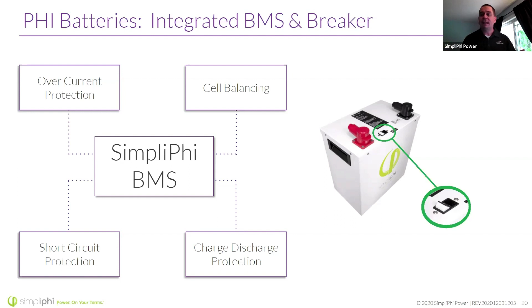When we talk about batteries, we talk about a C rate. The C rate is the charge rate, the rate at which a battery is discharged or charged relative to its maximum capacity. In the lead acid world you may see C5 or even C10 rates, meaning that battery can only really charge or discharge over 5 or 10 hours, which is a really long time. A C1 rate means the entire battery could charge or discharge in 1 hour, which is very fast. Our batteries are C/2, meaning you can charge or discharge the whole battery in 2 hours, which is pretty fast. It's important to understand this rate is relative and holds true for any size of the bank.